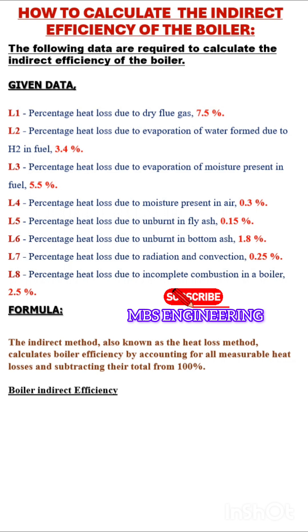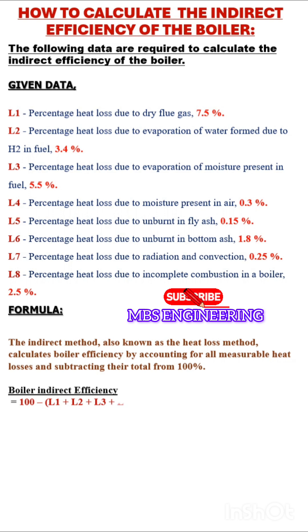The boiler indirect efficiency is equal to 100 minus the sum of the heat losses: L1 plus L2 plus L3 plus L4 plus L5 plus L6 plus L7 plus L8.